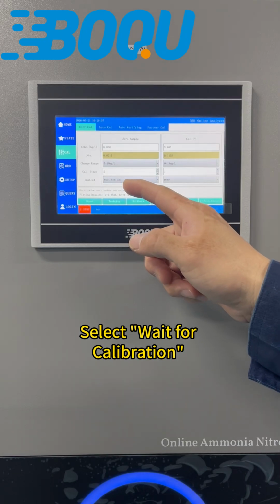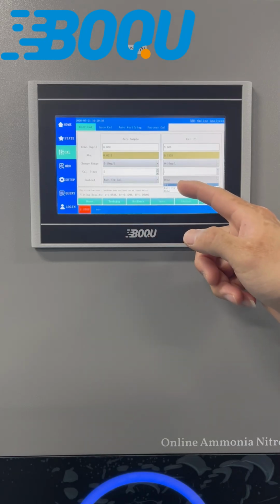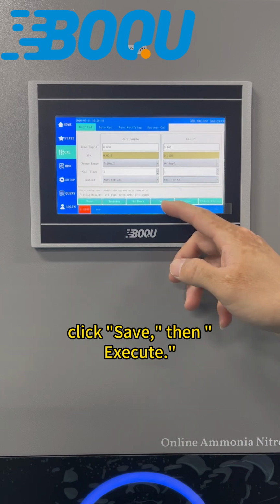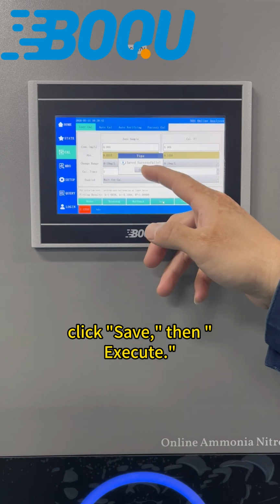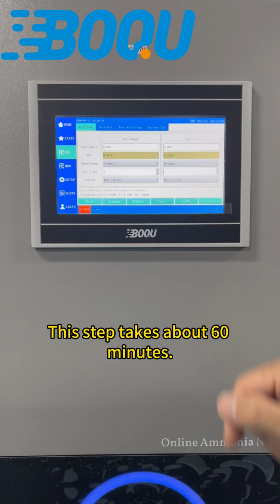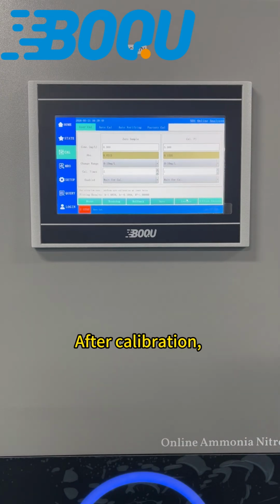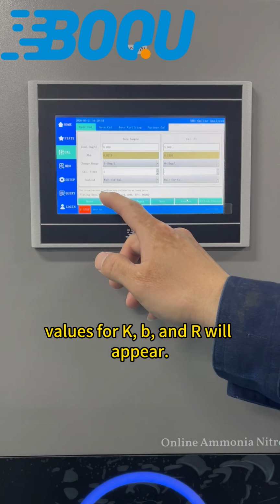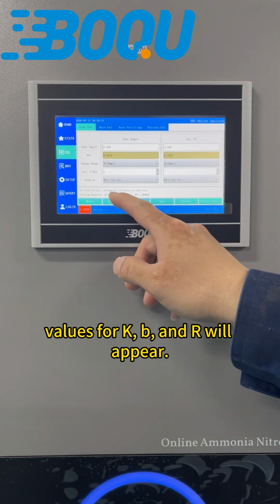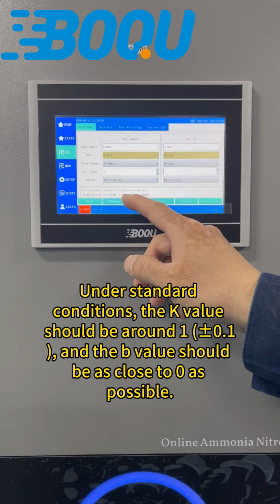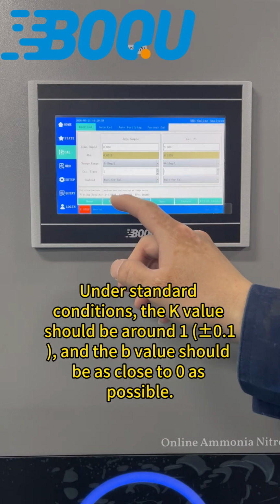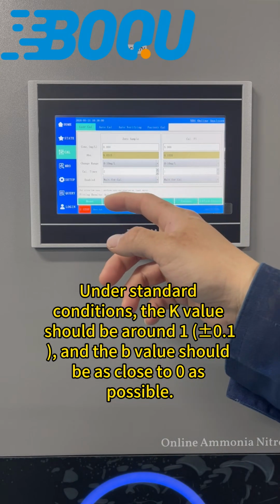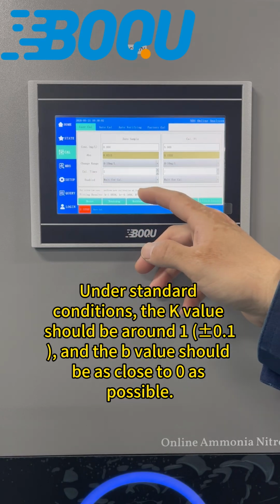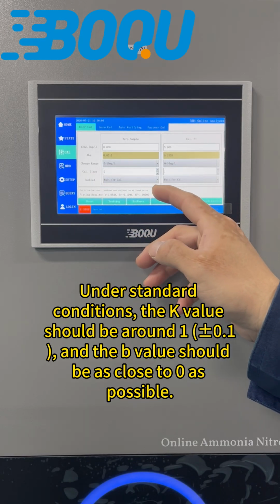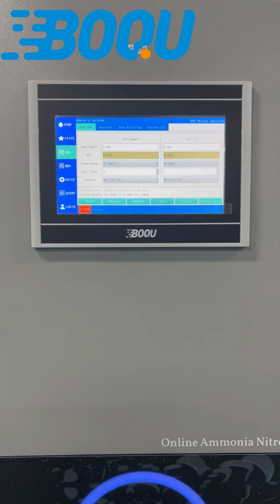Select Wait for calibration. Click Save, then Execute. This step takes about 60 minutes. After calibration, values for K, B, and R will appear. Under standard conditions, the K value should be around 1, plus or minus 0.1, and the B value should be as close to 0 as possible.